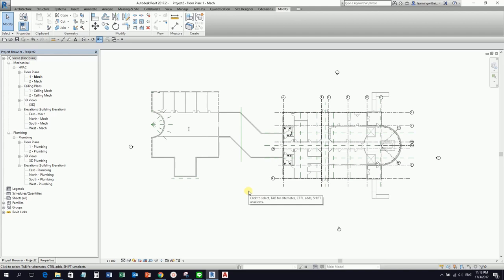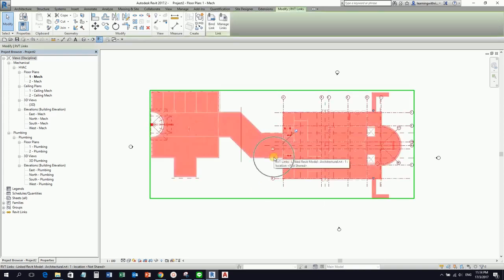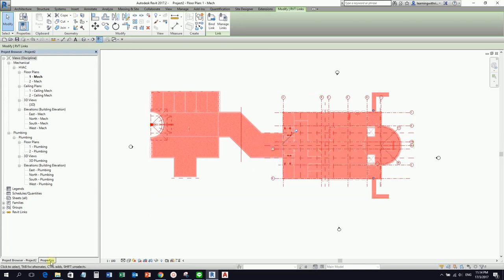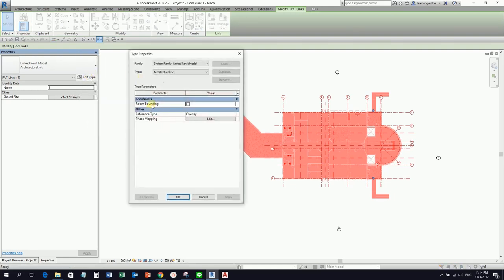Since we are going to place a space in our mechanical model, and this is a linked model, select the link model and from the Properties go to Edit Type. Make sure Room Bounding is checked. If you do not check Room Bounding, you will not be able to place the space properly. This enables us to place the space correctly inside our project. Just check this and then select OK.